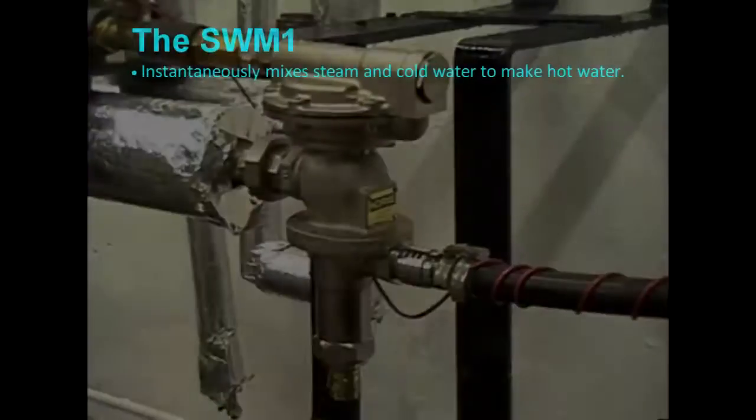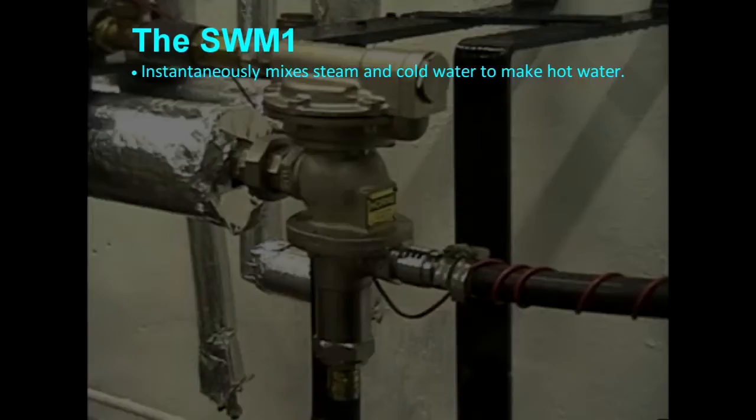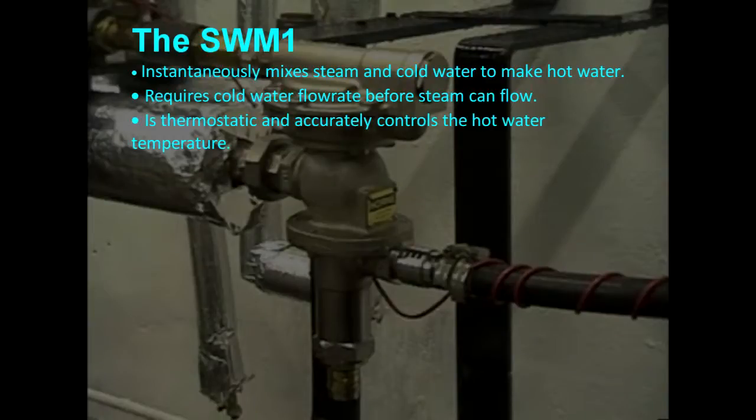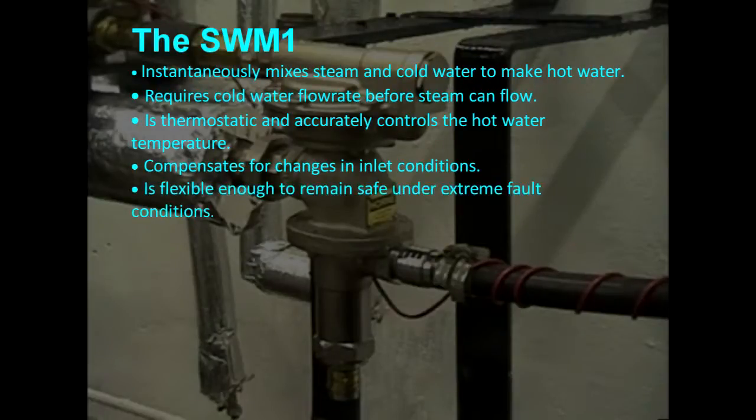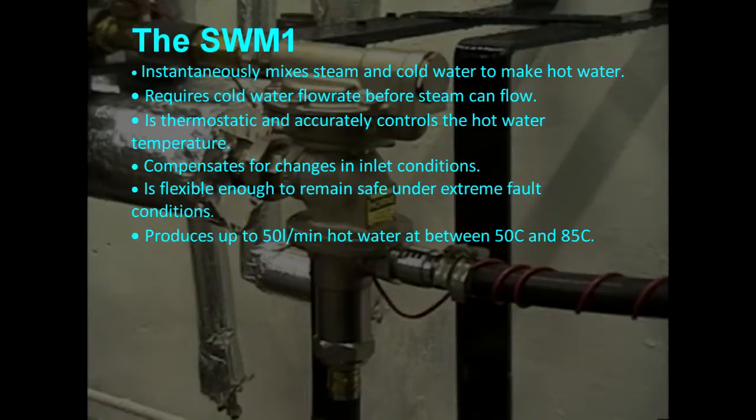The SWM1 instantaneously mixes steam and cold water to make hot water. It requires cold water flow rate before steam can flow, is thermostatic and accurately controls the hot water temperature, compensates for changes in inlet conditions, is flexible enough to remain safe under extreme fault conditions, and produces up to 50 liters per minute of hot water at between 50 and 85 degrees C.